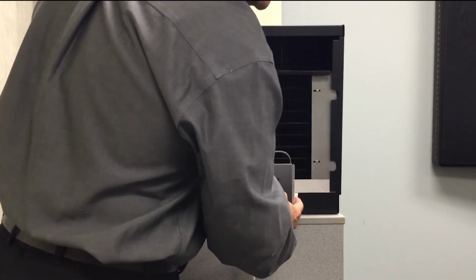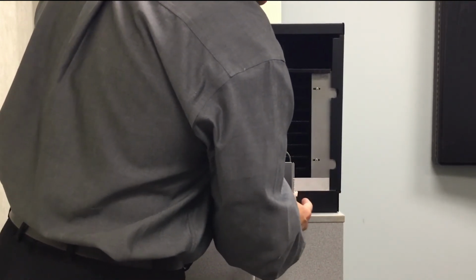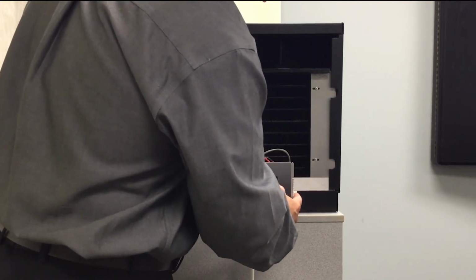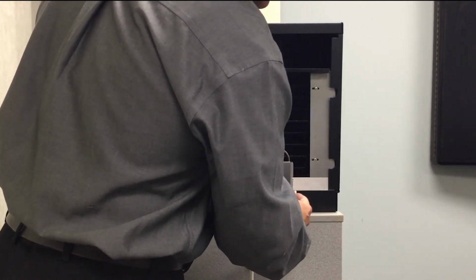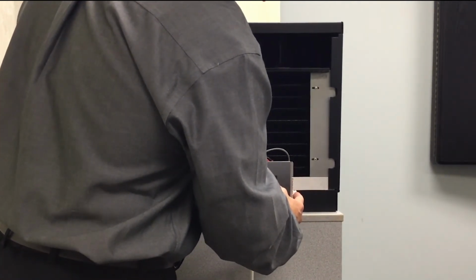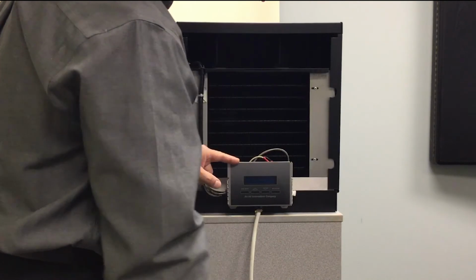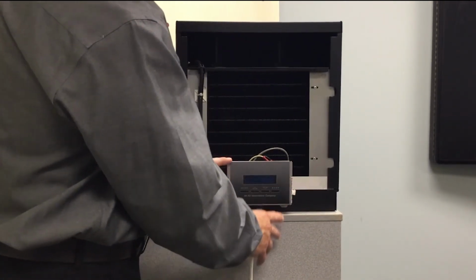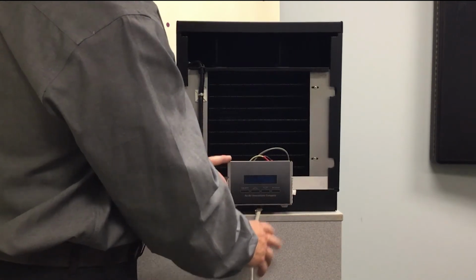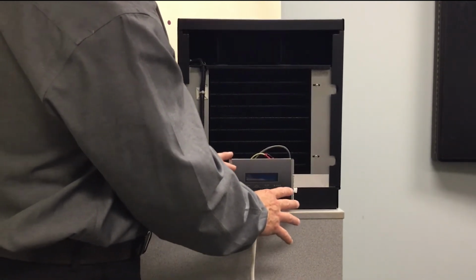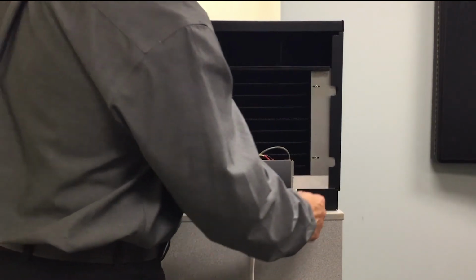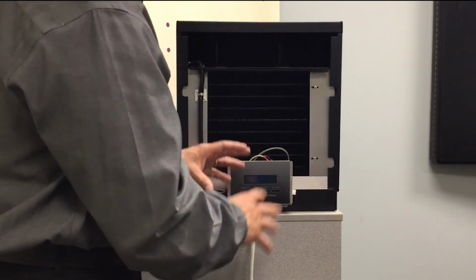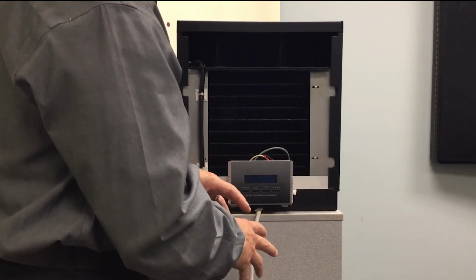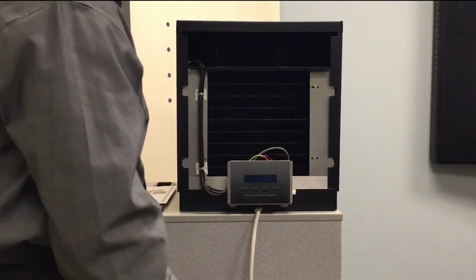One other feature here that you'll notice is the humidifier connection. There's a little white, what's called a Molex connection here on the side of this control panel. This is where, if you had an optional Wine Guardian standalone humidifier, you'd plug in the power and control cable. And then this goes out to your remote humidifier and all the control ends up being at this device. So you'd set your adjustments here for what humidity level you wanted, and this also powers that humidifier, so you don't have to have a separate power cord connection for that device. It's all controlled right here at this main control.